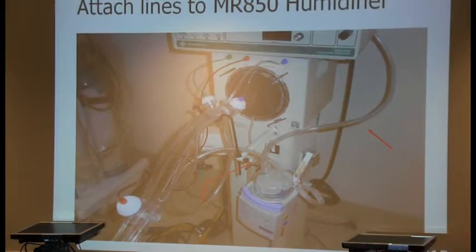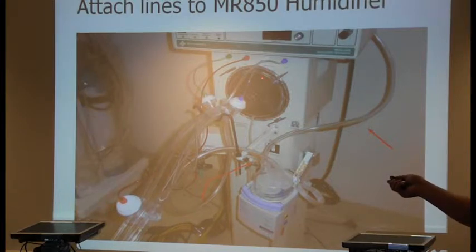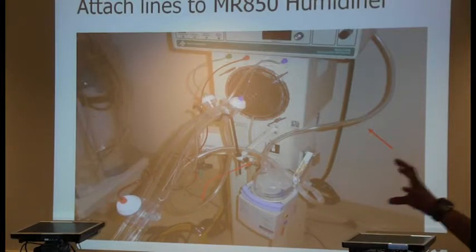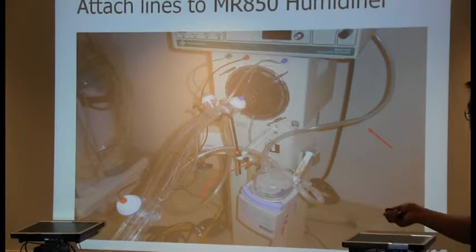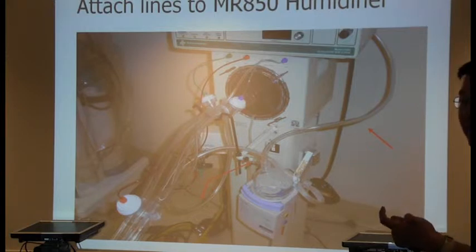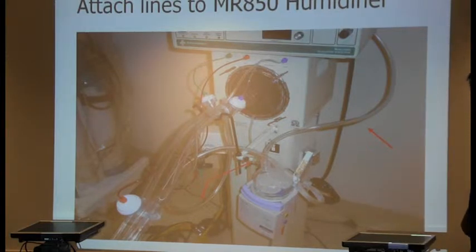You go back. The easiest way to do it is to check these lines. If you don't feel anything loose, just disassemble the bellows, because a lot of times the bellows don't set correctly, and you may have a micro leak. Your water trap: make sure that on the bottom of the water trap you close the valve off, because air is going to leak out that way.